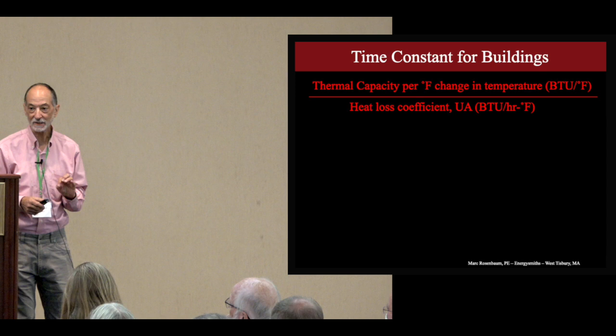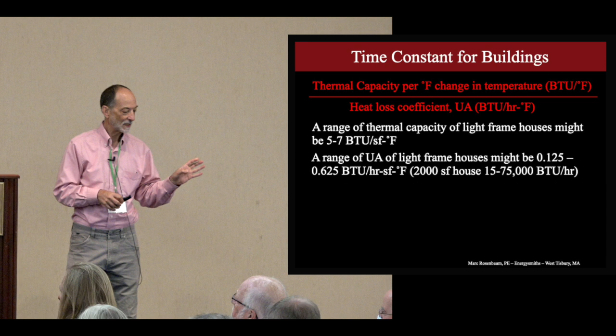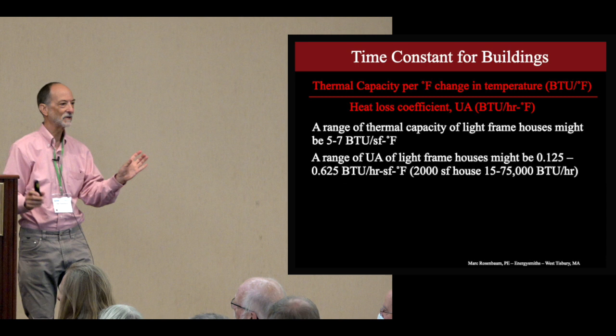A range of thermal capacity for light frame wood buildings is between 5 and 7 BTUs per square foot per degree F. A range of heat loss coefficient, and the units may not be familiar here, 1/8 to 5/8 BTUs per hour per square foot. But here's my example. A 2,000 square foot house, maybe somewhere between 15,000 and 75,000 BTUs an hour. Yes, passive houses are lower, and really, really bad houses are higher, okay? But most of the buildings that you've ever seen are in this range. So far, so good? You have to trust me on this one. So a time constant of light frame houses would be somewhere between 10 and 50 hours, depending on the heat loss of the house.